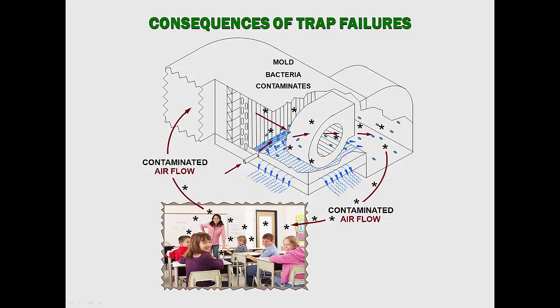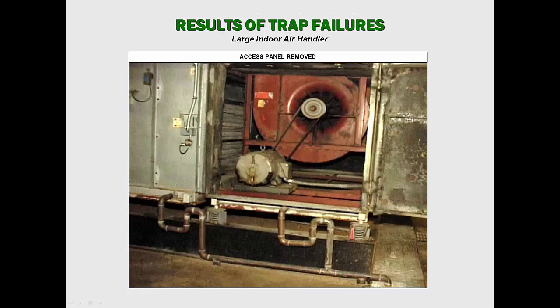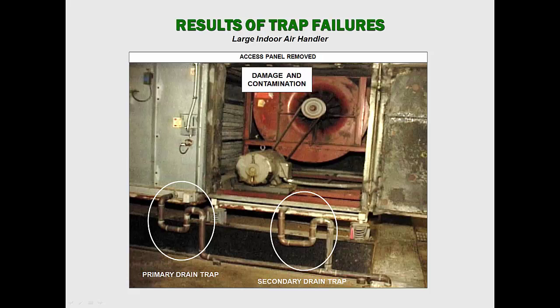The photographs that follow show examples of the damage that condensate trap failures cause to equipment and buildings. These photographs show a small rooftop air conditioning system which was operated without a trap as a result of an inherent trap deficiency and an unwise field practice. The damage and contamination shown are the results of flooding caused by a blocked trap, and were accelerated by condensate blowing and possible flooding when the trap was removed. This large indoor air handler has two traps, primary and secondary, that exhibit both inherent and design deficiencies. Observe the damage and contamination caused by these traps.